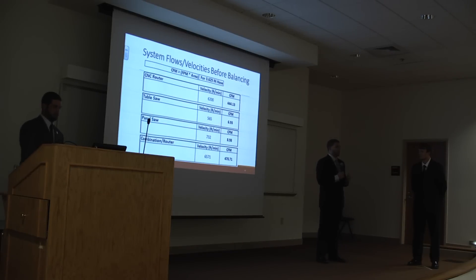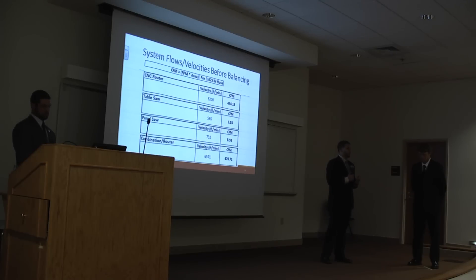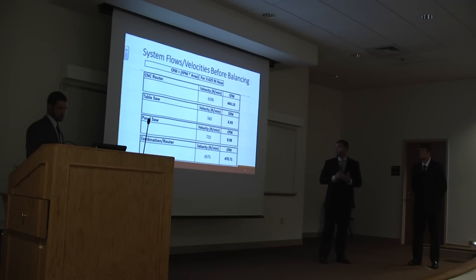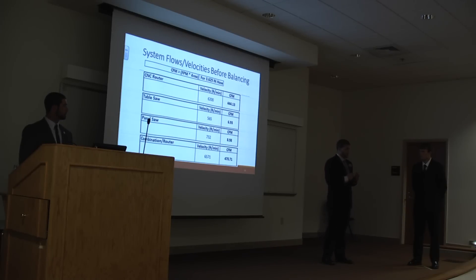Before we could do a line balancing for this system, we had to determine the flows currently at each machine. To do that, we used an anemometer, which measures the velocity in feet per minute. You multiply that by the area of the pickup tool, and that gives you your flow in cubic feet per minute. At the CNC router, you've got 444 CFM. At the table saw and the panel saw, you have about 6 to 8, and at the combination router, you have 470. The CNC router and the combination router have above 6,000 feet per minute velocity — which we'll get to later — that's too high for the material we're going to be cutting. The table saw and panel saw are extremely low for the material that's going to be handled.